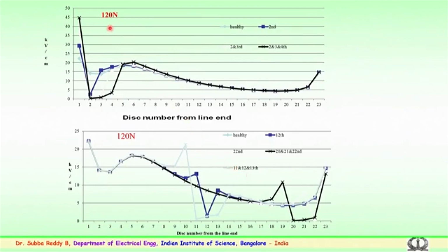This shows 120 kilonewton discs for a 400 kV system, where the potential gets modified. A comparison has been done for the healthy strings and the strings which are faulty, particularly considering faults in the second and third disc near the line end. What happens? You can see the green curve, which shows the healthy conditions. The potential gets immediately modified for the fault conditions. If the fault is at second, third, or second, third, fourth, you can see this last one is the second, third, fourth fault condition, and this is for the fault condition of the second and third.